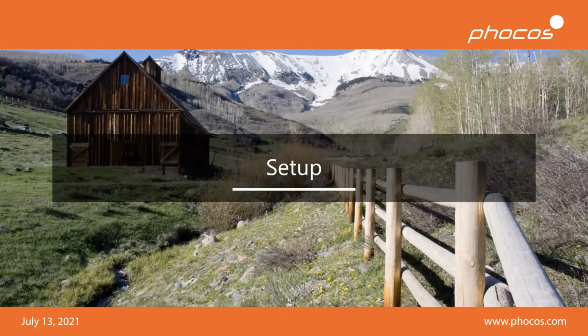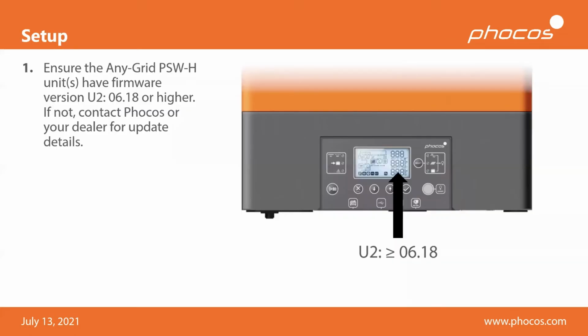Now I'd like to go through the setup process. You'll see it's quite simple and not very involved. The first step is to ensure that your AnyGrid PSWH units have firmware version 6.18 or higher for the U2 firmware. There are 3 firmwares on these devices, and the U2 firmware is the one that's responsible for the display unit and for all of the communication functions. This is where we require 6.18 as a minimum version to make sure that the compatibility is there between the AB-PLC and the inverter.